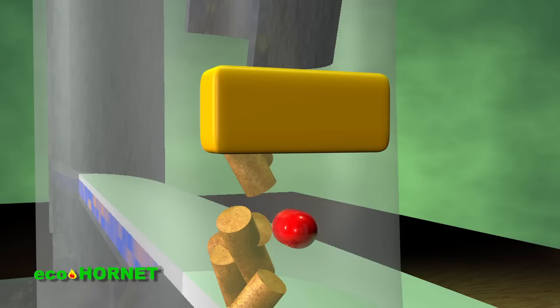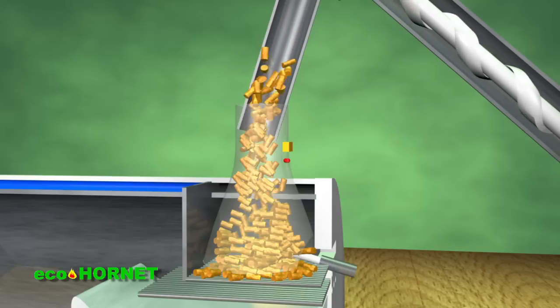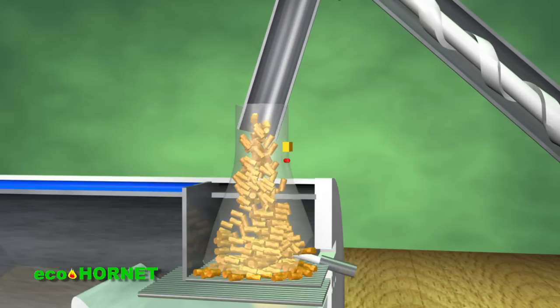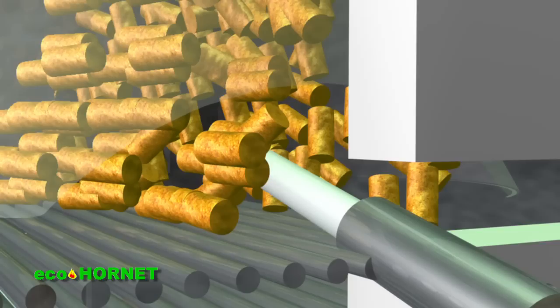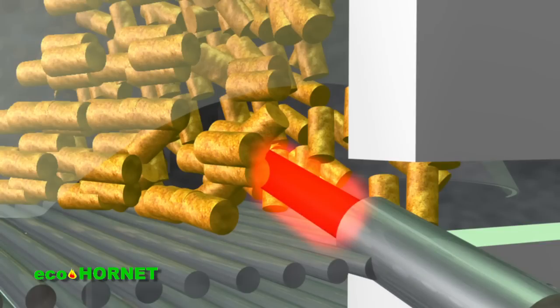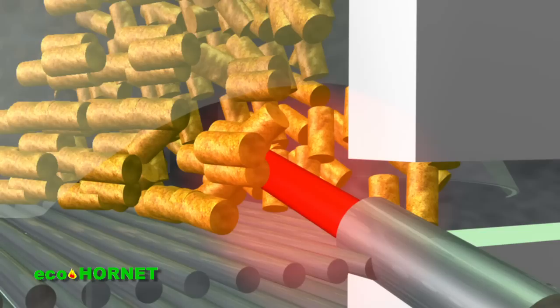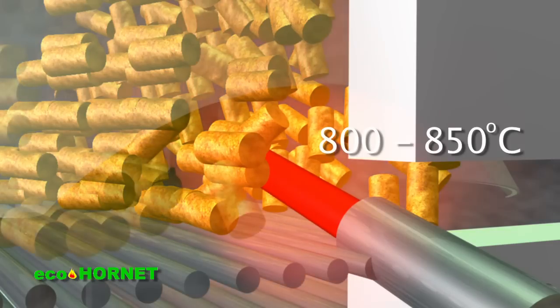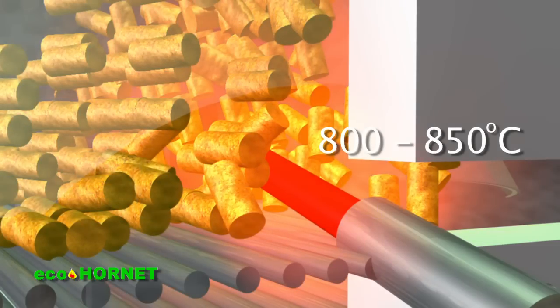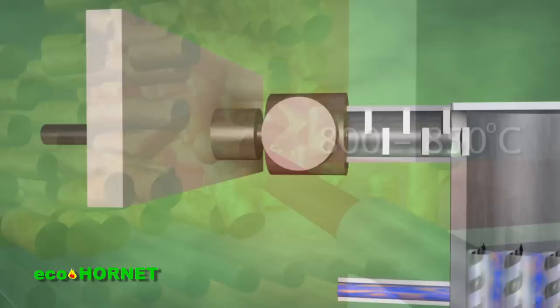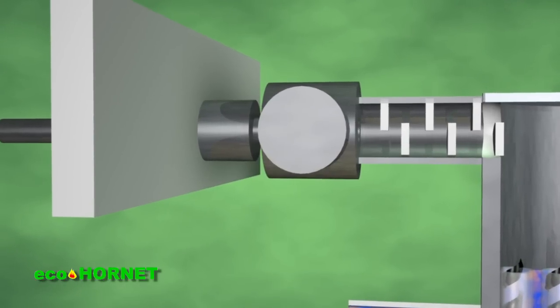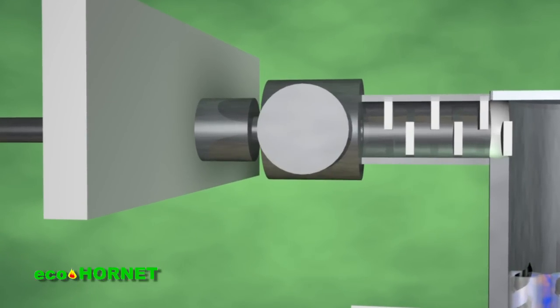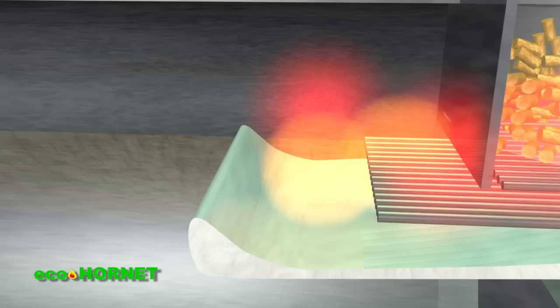When the combustion chamber is loaded, the sensor stops pellet supply and the combustion resistor with 24 volts is automatically activated. The resistor instantly reaches 800 to 850 degrees Celsius, is covered with pellets that ignite, and the exhaust starts to function.